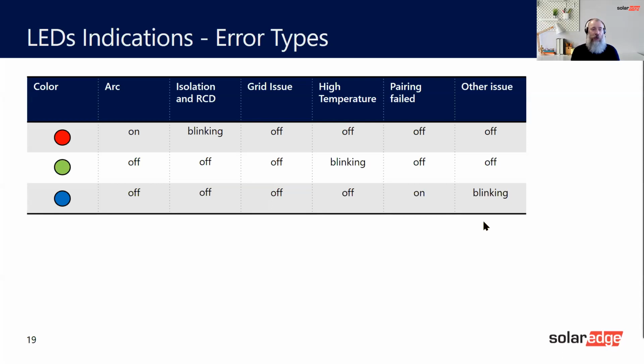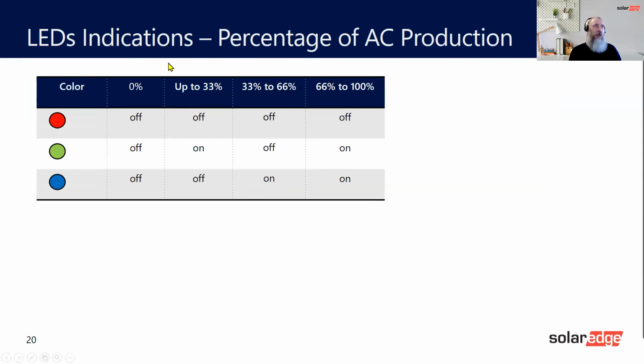Because we don't have a screen on it, we have an LED underneath, and this basically allows you to understand what the inverter is doing. The most important one of all is the blue one. Okay, this is looking at different things. The blue being on is communication. So this is pairing failed: off, off, on. But generally the blue one is on permanently, and the green one is either blinking or solid. So loads of different things. This is the error types. This is the percentage of production.